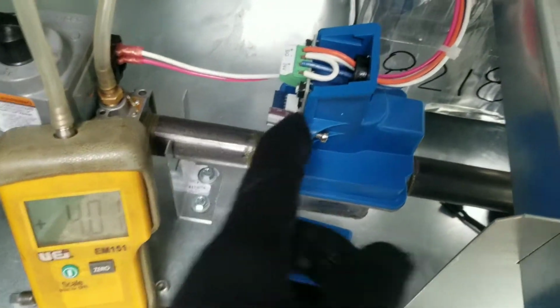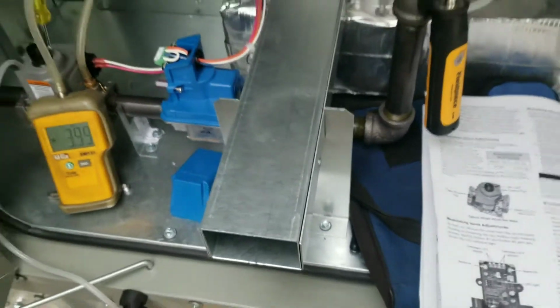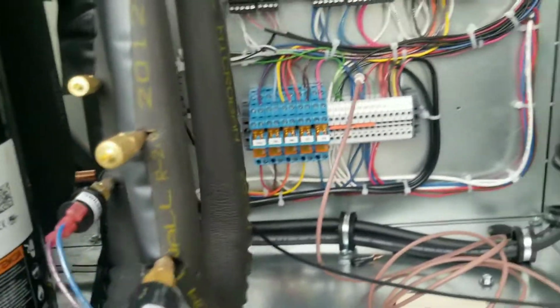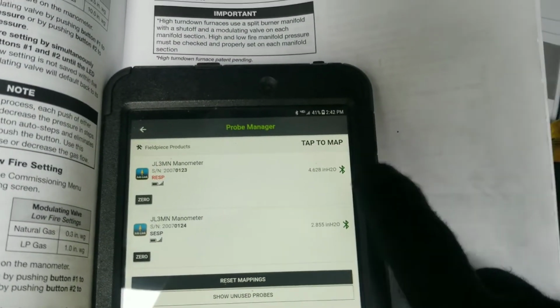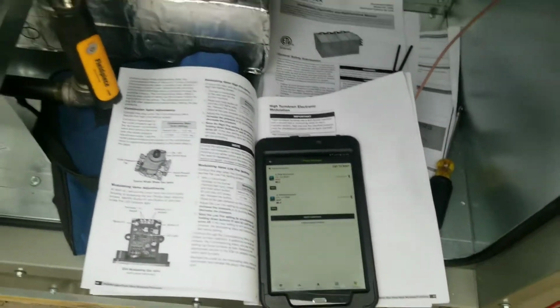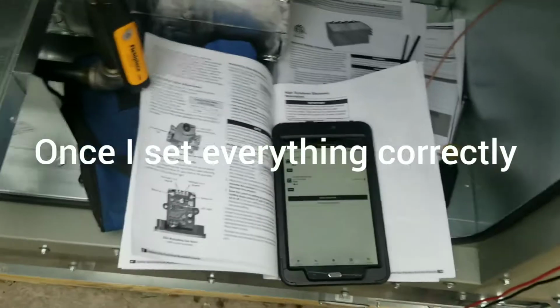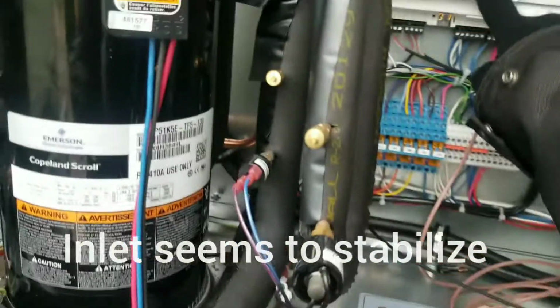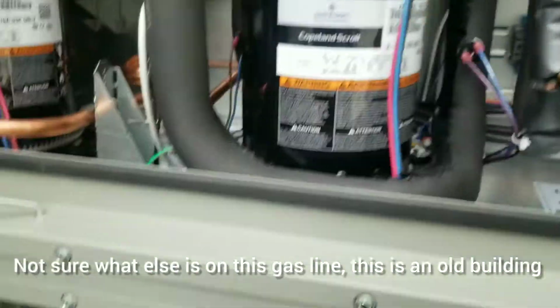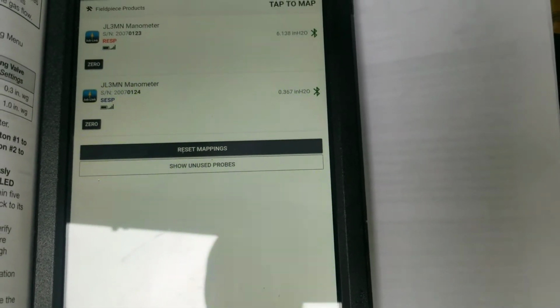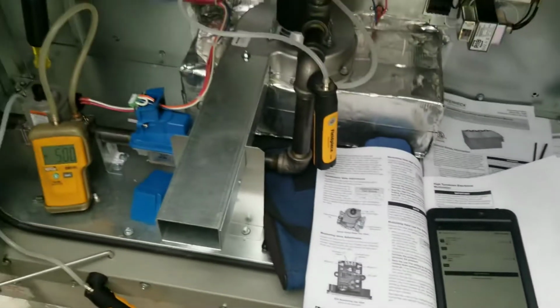Verification mode. Combustion fan sped up, and 3.2 water column. It was a 3.5. It's dropping down. To save the set points in this, you have to hit both buttons simultaneously. So that's what I did wrong. And my inlet gas pressure is affecting me still. That's going to be an issue. We're going to have to dig into that and make sure we've got enough gas pressure, because I was at 3.5, and then as my inlet dropped down, everything else dropped down, and I dropped down to low fire, 0.33. So we're going to call this one good for now.